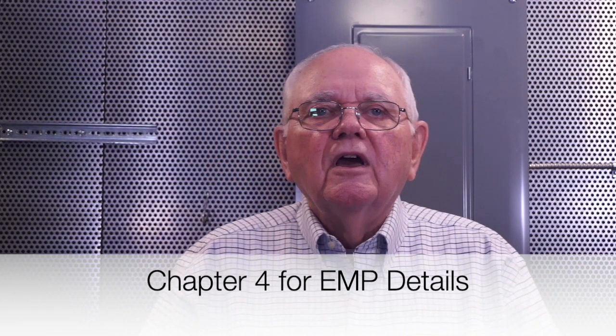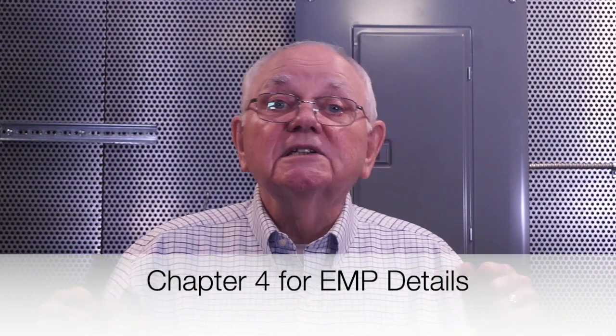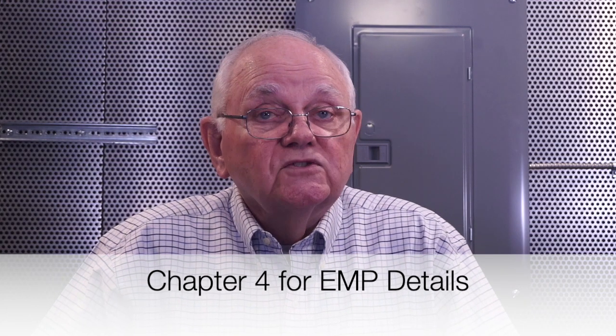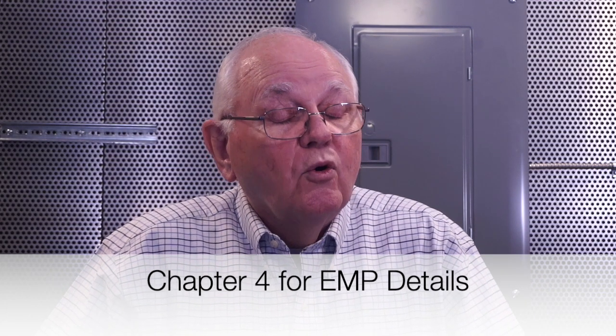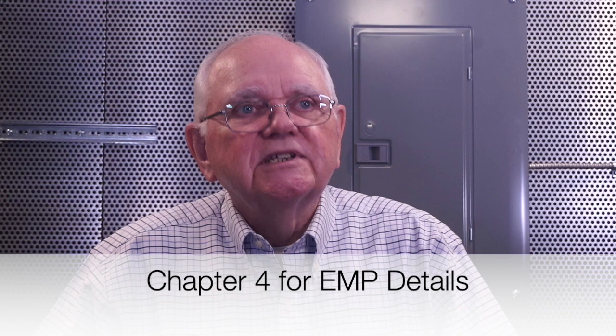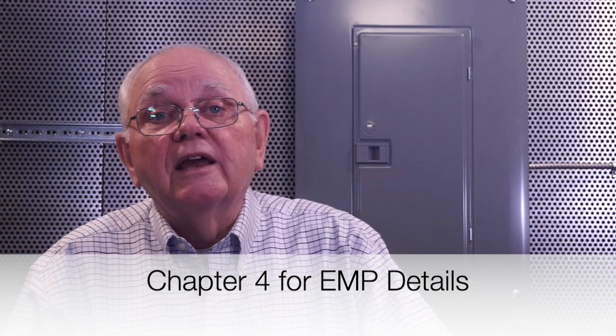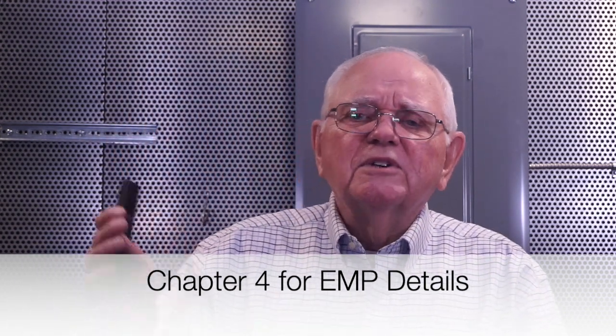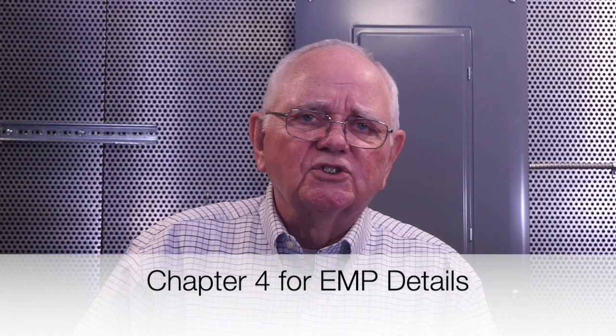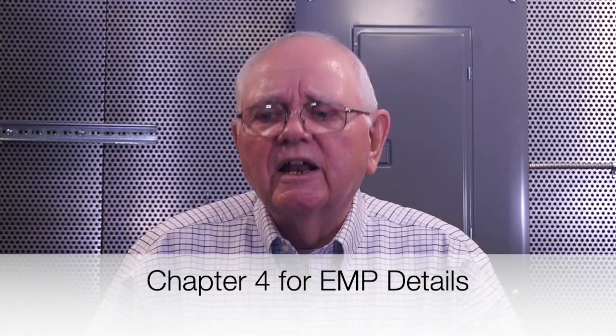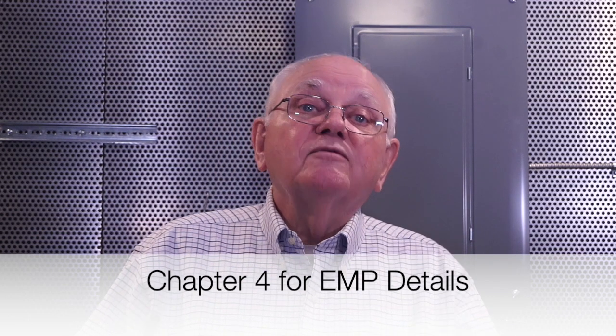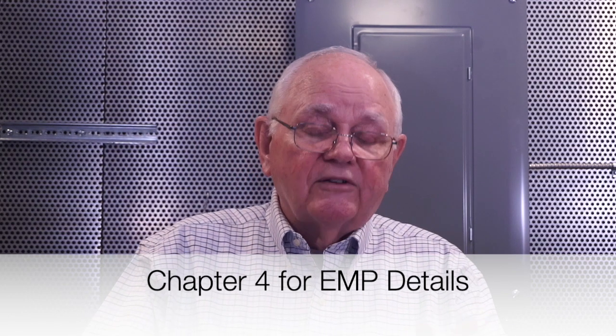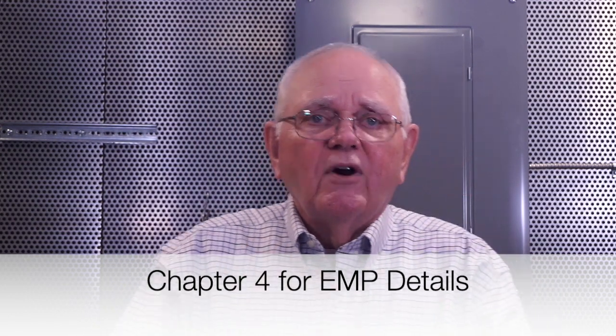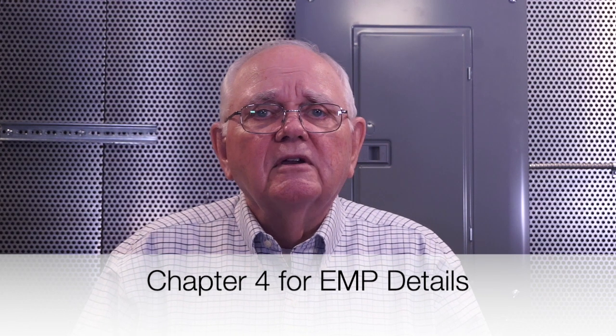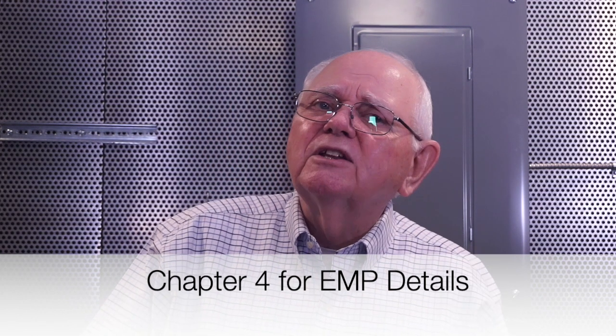And so forth. Well, we have to designate an electrical maintenance program coordinator. It tells us in 70B. Somebody to run the program, right? Go out and make sure that we set up the program properly, have procedures developed, workers are qualified, and all of that. The things that we have to do as part of that program: that coordinator is responsible to go out and get inspections done on that equipment. What's its current condition of maintenance right now?